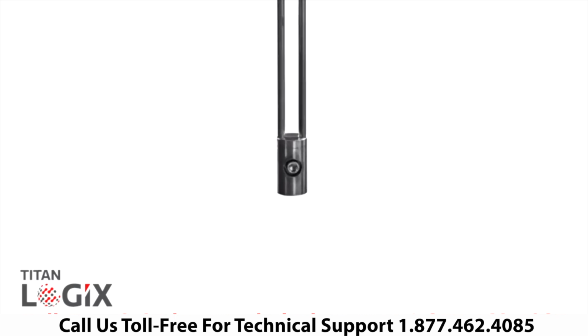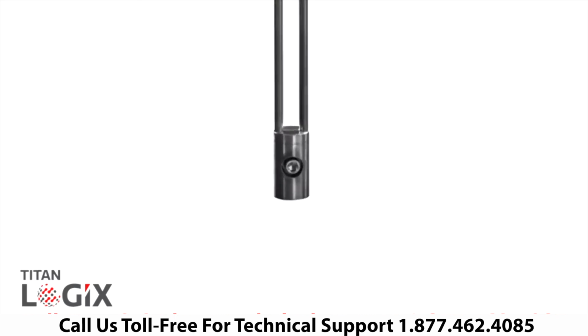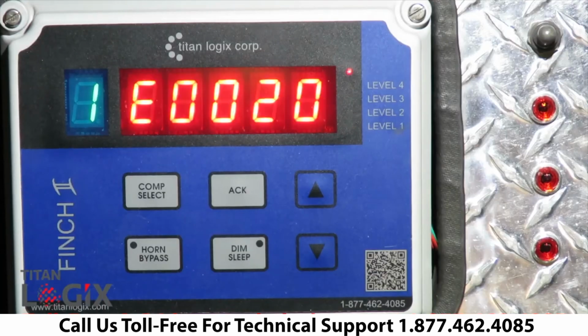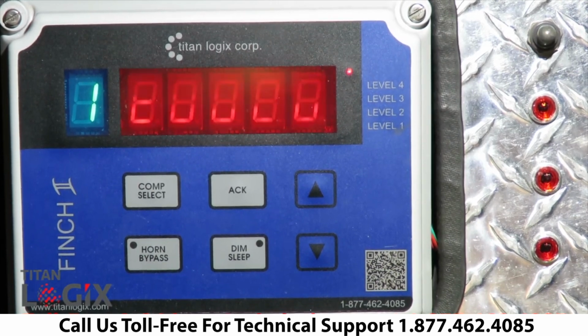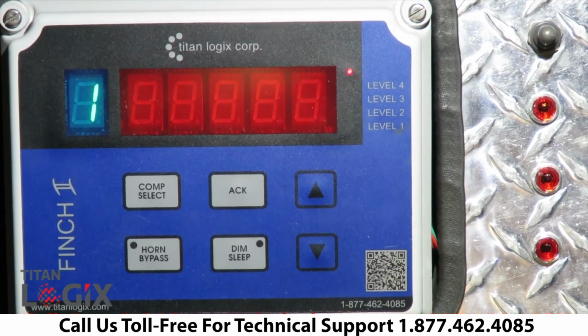A loose shorting block at the bottom of the probe can also be a problem. Remove probe and check for loose or missing set screws. Finally, if the E20 code is constantly displayed on the FINCH II, then there is an internal problem in the TD transmitter. The transmitter needs to be replaced or repaired.